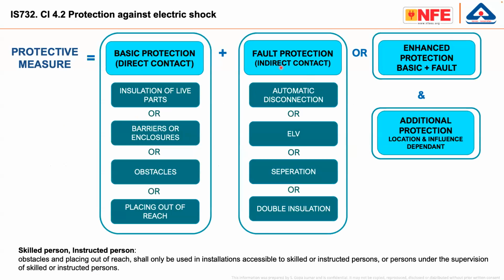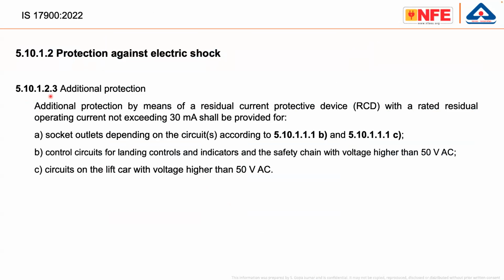Basic protection is already explained. Fault protection we will go to later, and additional protection. For example, this particular clause 5.10.1.2.3, additional protection. Additional protection by means of a residual current protective device with a rated residual current not exceeding 30 milliampere shall be provided for basically the car electrical single phase. Sometimes people get confused that a 30 milliampere RCD is already provided on the lift car, so other RCDs are not required. Sorry, it is not like that. It depends what kind of protective measure you are supposed to achieve. This is an additional protective measure, a 30 milliampere RCD for the single phase supply, especially with a type A RCD, because most of the time we use LED lights. You cannot violate this. This is a mandatory requirement.